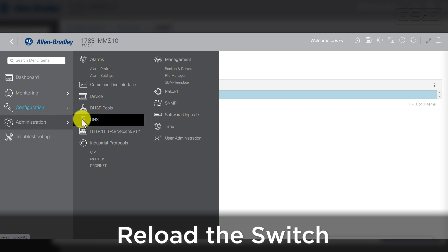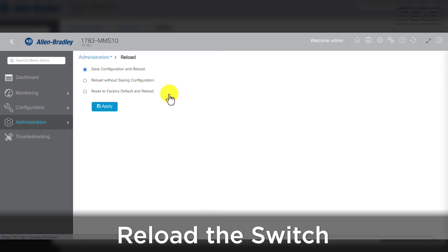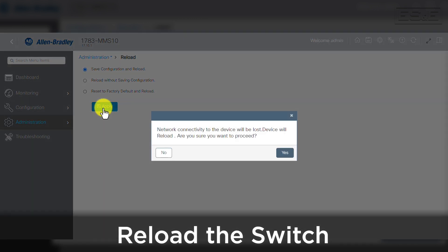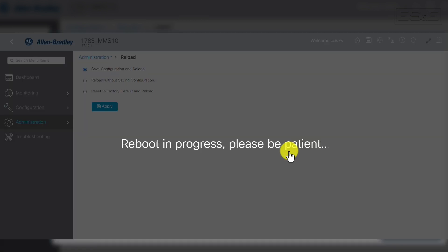Now we can move to the third step where we need to reload the switch. Reloading the switch configuration is a step that is often overlooked. This step will force the current configuration into the switch and reboot the switch to ensure it maintains the configuration through a power cycle. This may take several minutes and it does stop all communications, but it is necessary. Thanks for watching and if you have any questions please contact your local ES&E Account Manager or Automation Specialist.